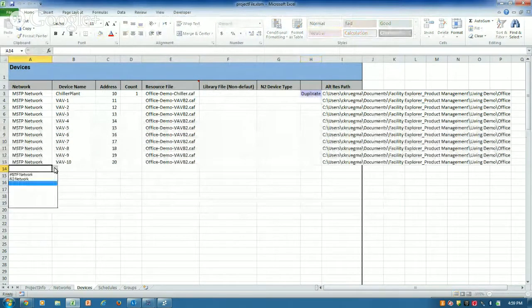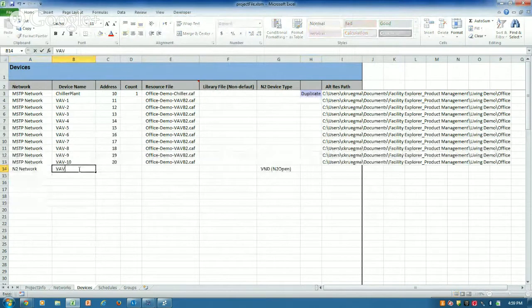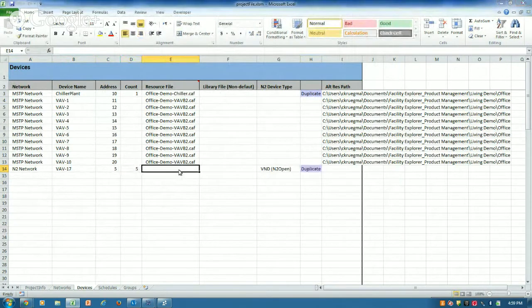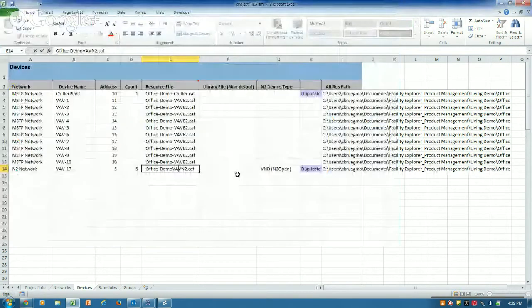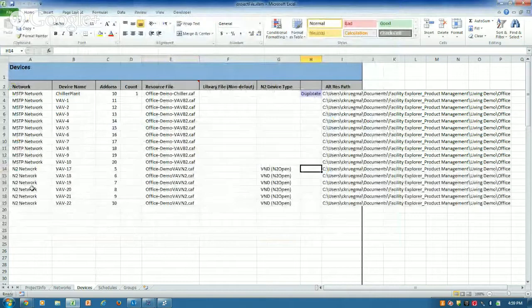Let's say I also add an N2 network here with some VAV boxes on it: VAV-17, and I've got 5 of those at N2 address number 5, plus 5 additional ones. I'll navigate to where I have my VAV N2 application and hit duplicate to add all those devices.